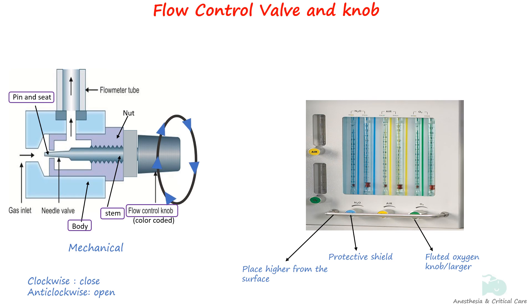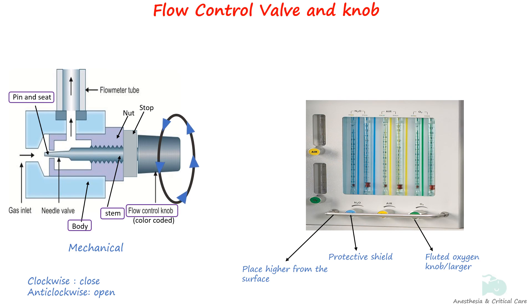The flow control knobs are turned counterclockwise to open gas flow and clockwise to close it. When the valve is closed, the pin fits into a metal seat and no gas flows. When the stem is turned counterclockwise, an opening is created between the pin and the seat, and gas starts flowing into the flow meter. There are stops for the closed position and maximum opening position, which prevent damage to the pin or disengagement of the stem from the valve body.